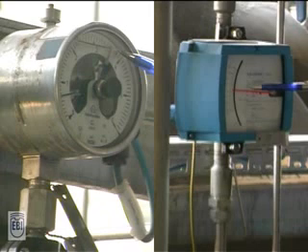This shows the high contact pressure gauge in front of the orifice which serves as a leakage control of the primary gas seal. A flow indicator with a low flow alert controls the function of the backup seal. The leakage flow of the product gas towards the flare.